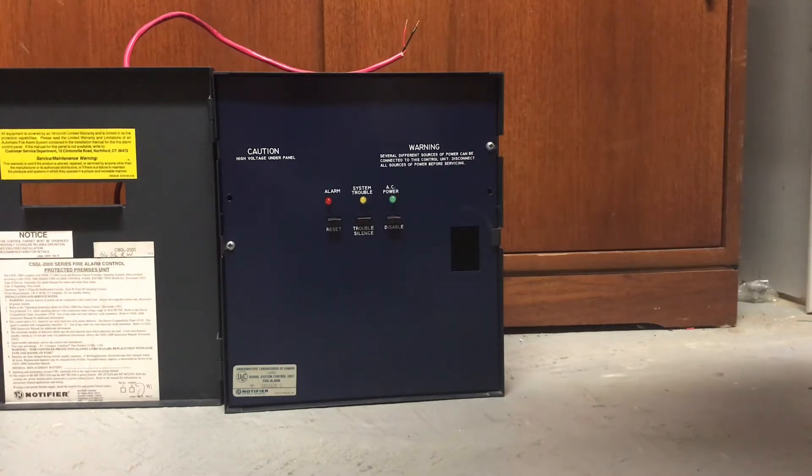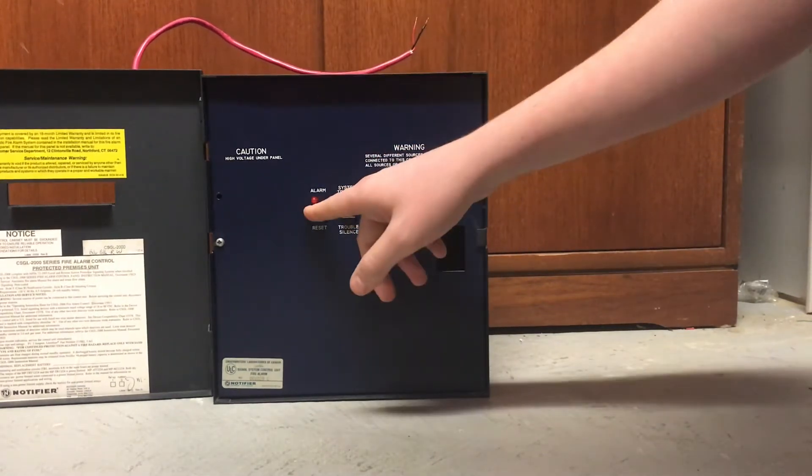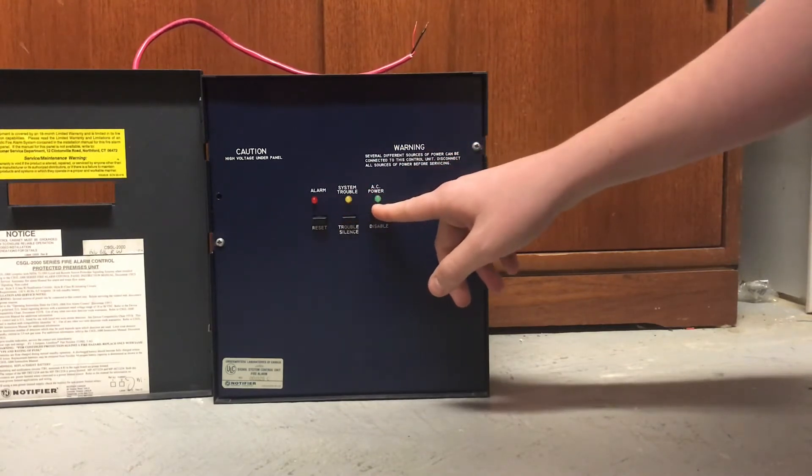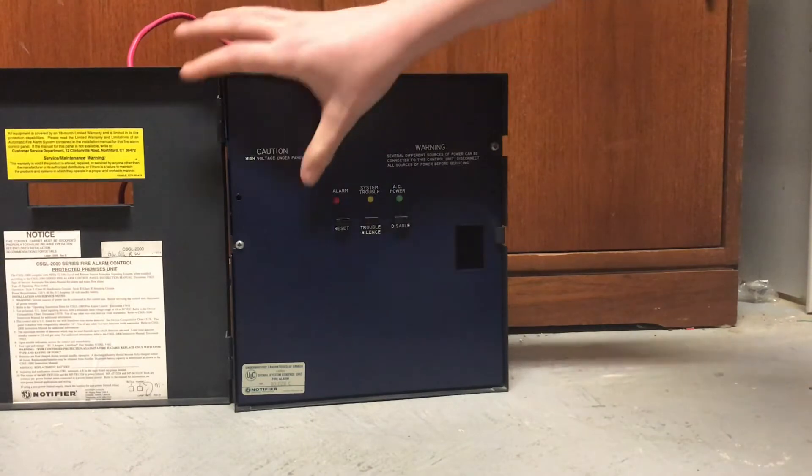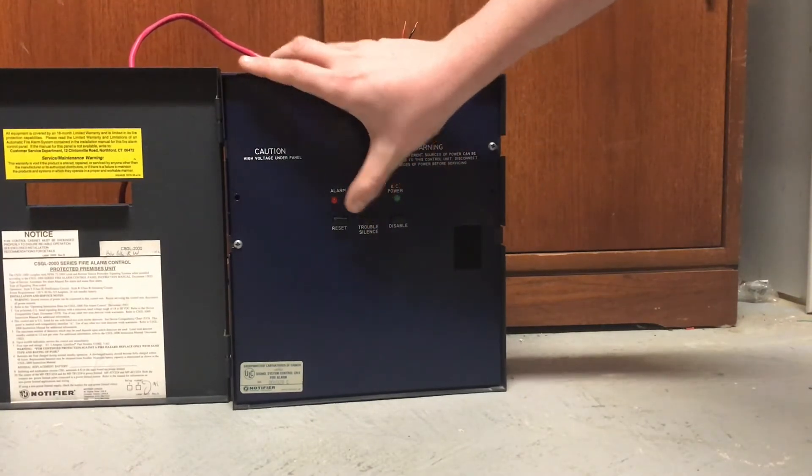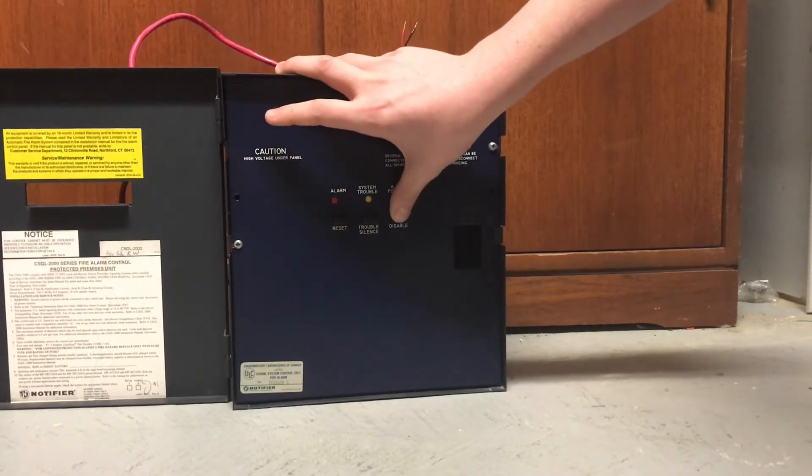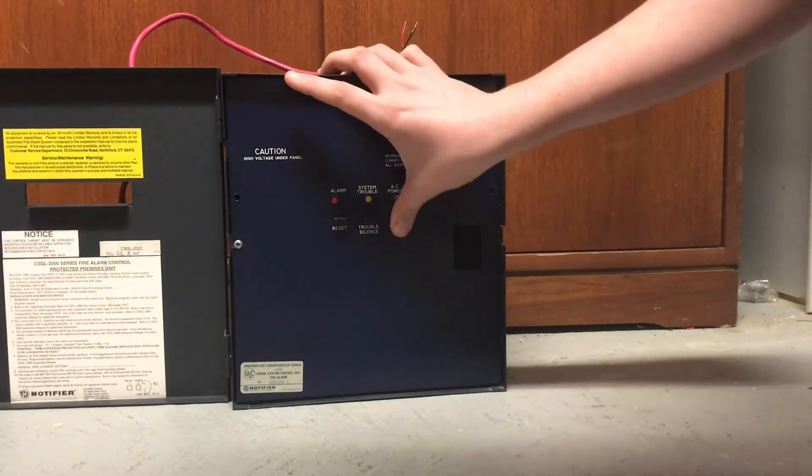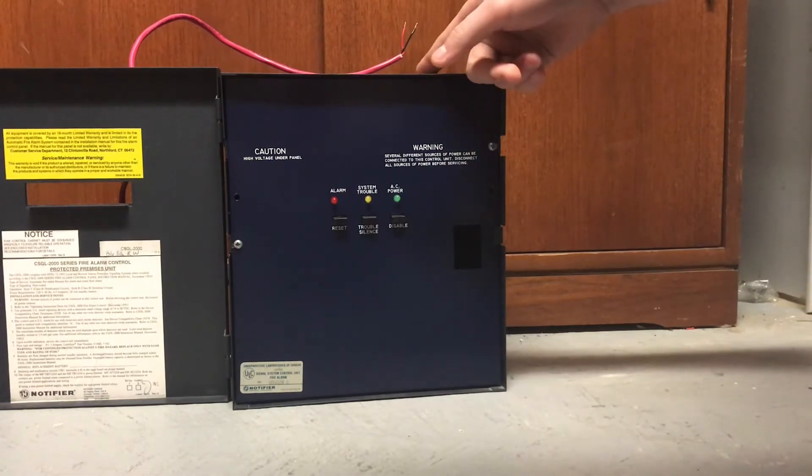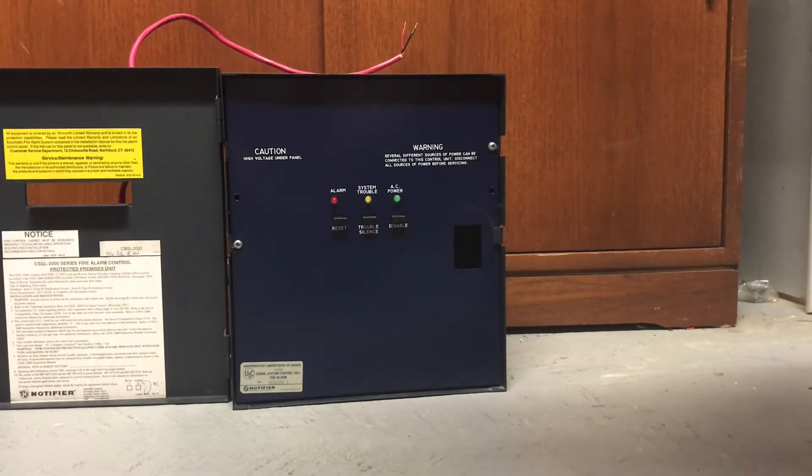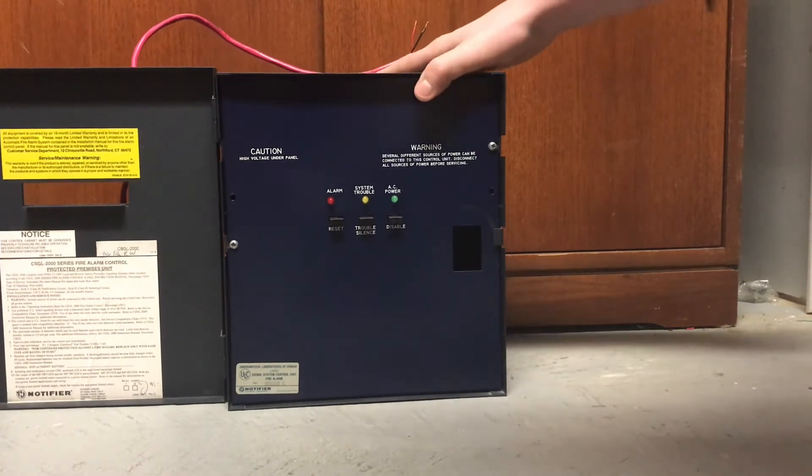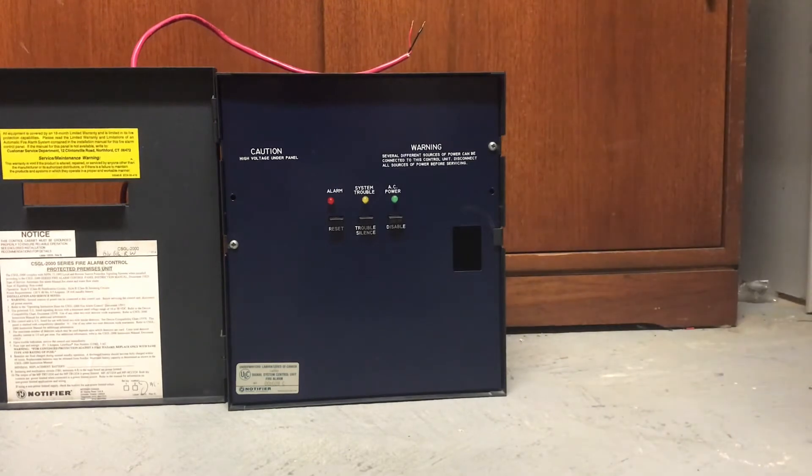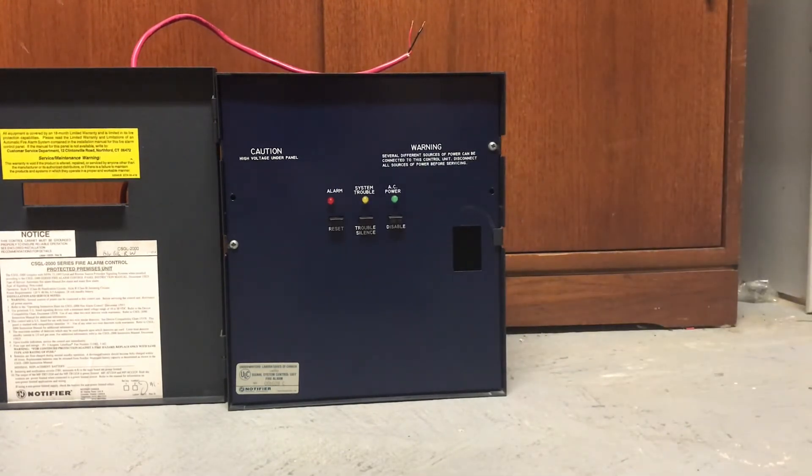So this panel is a one-zone, one-NAC panel with three LEDs. You've got an alarm LED, a system trouble LED, and an AC power LED. And then these three buttons here, there's one for trouble silence, reset, and disable. The trouble silence and disable buttons are kind of toggle buttons, so they'll hold in place. This panel has a date code of 1995, so it is well before ADA, and it has no coding options, it only has continuous. So I am going to jump cut to when I open up the front cover here.